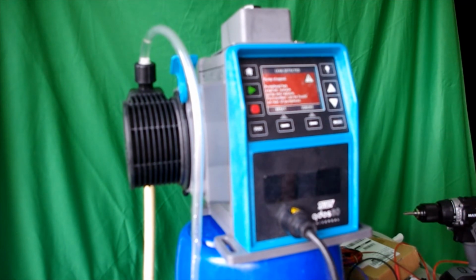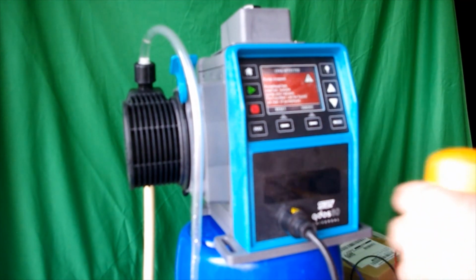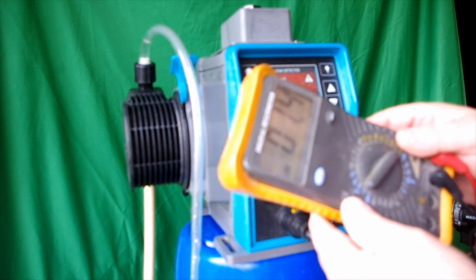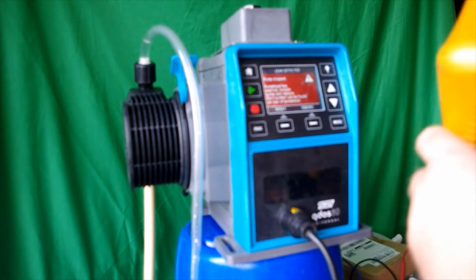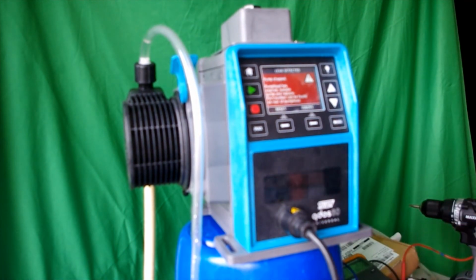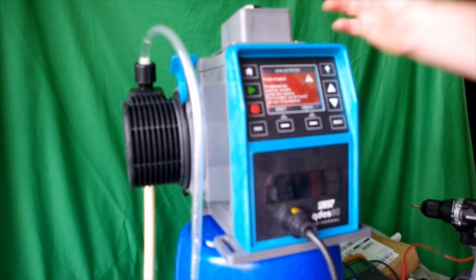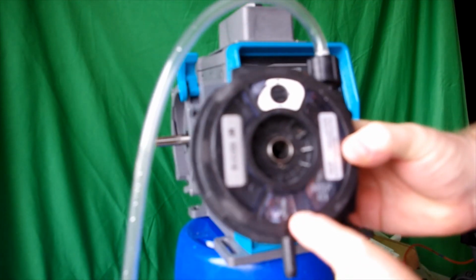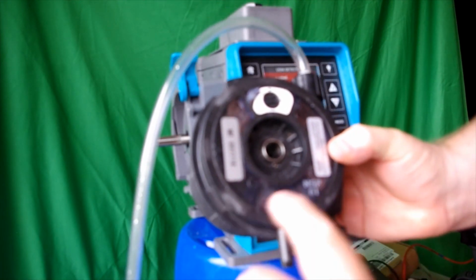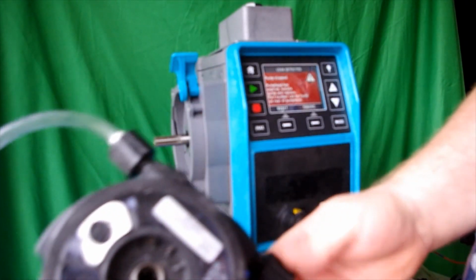So in this case, as I was mentioning, the multimeter picked up a contact from the alarm because the ReNu head picked up a leak and stopped the alarm. So that signal's gone to SCADA DCS system. So once you change your pump head, this is your pump head, and this is the leak detector port, actually. Once this detects the leak, the head's no more, it's expired, you would reconnect your hydraulic connectors, reinstall your brand new qdos pump head.